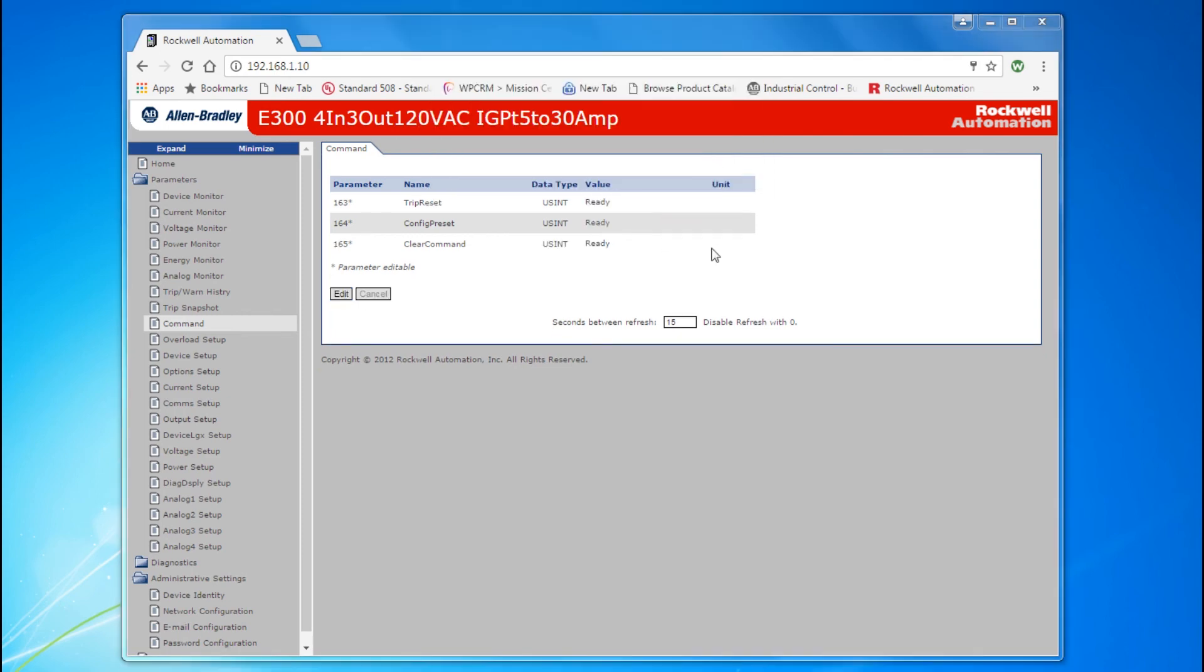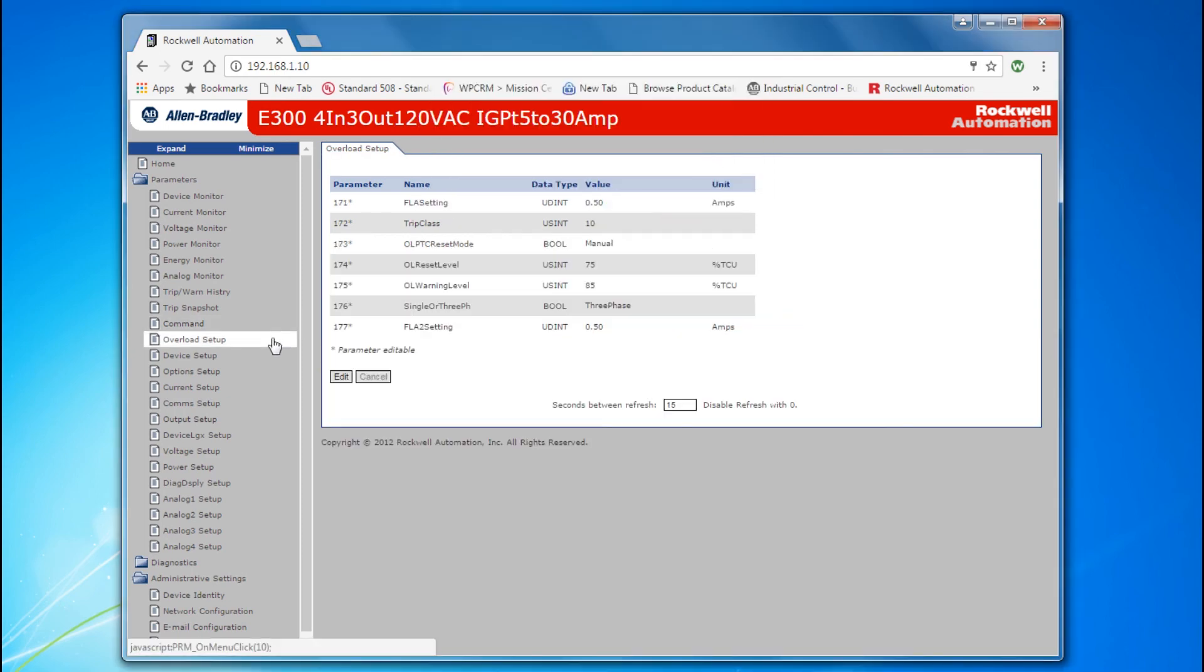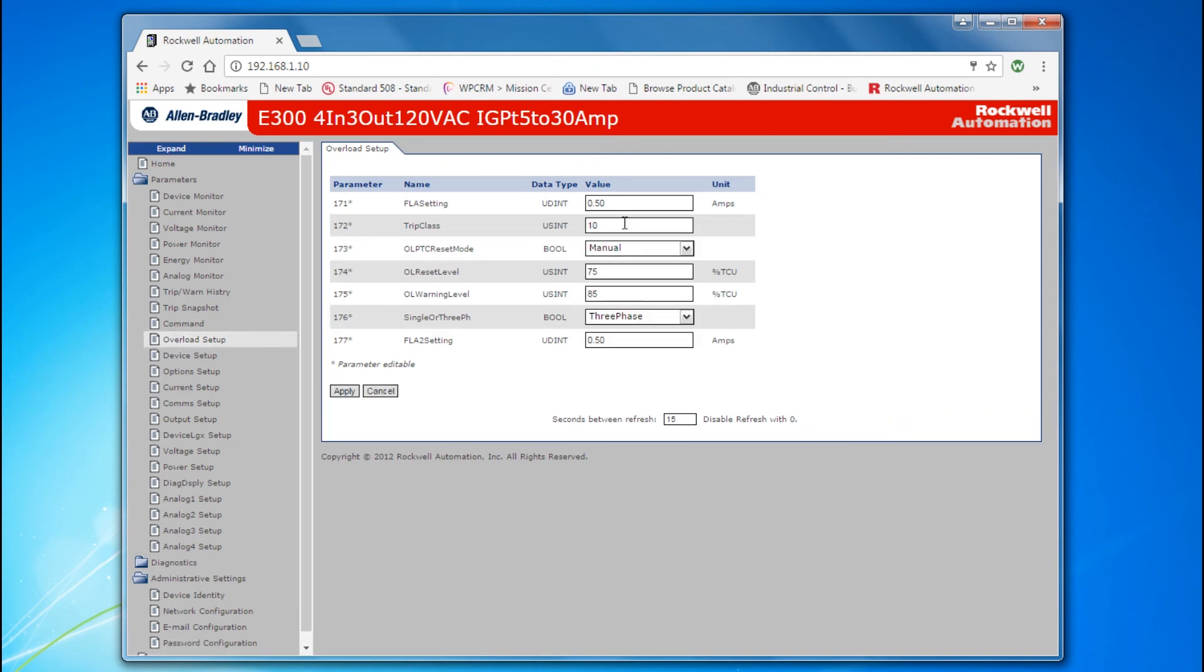Finally, navigate to the Overload Setup. Click the Edit button, and change the FLA setting, Parameter 171, to the proper value. Click Apply, then OK.